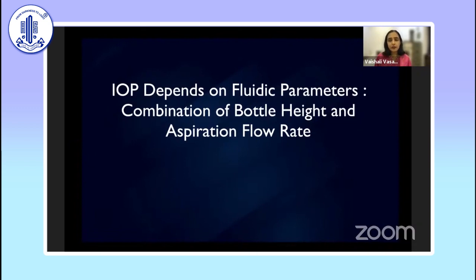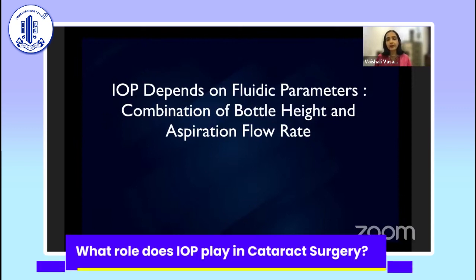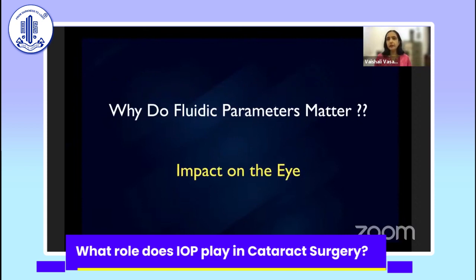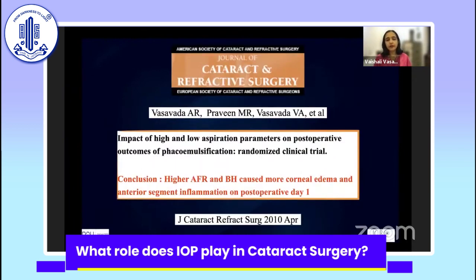Why are we talking about intraocular pressure during surgery? Because the fluidic parameters we use — specifically the combination of bottle height or irrigation pressure coming in, whether through a gravity-based or pressurized active fluidic system, and the aspiration flow rate — along with leakages through incisions, all affect the eye. Sometimes you can see it, sometimes you cannot. This whole journey for us started around 2010.